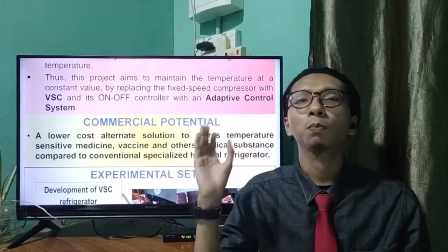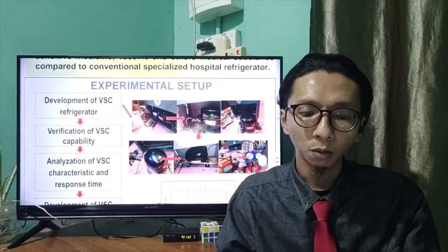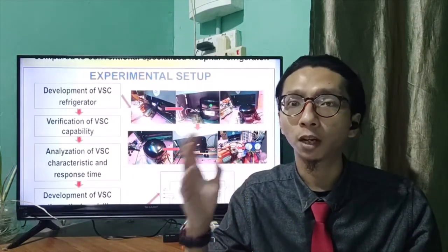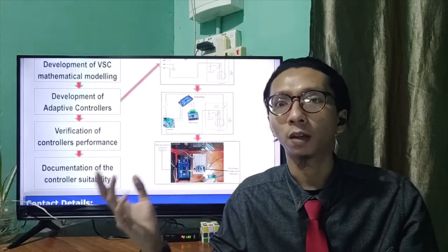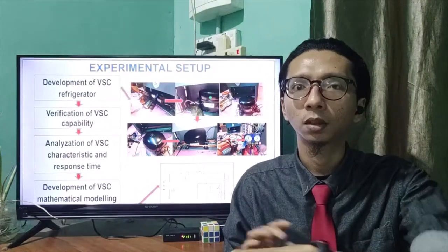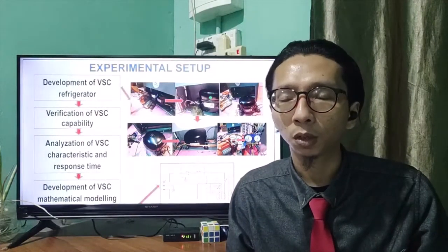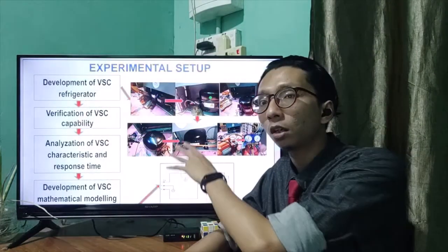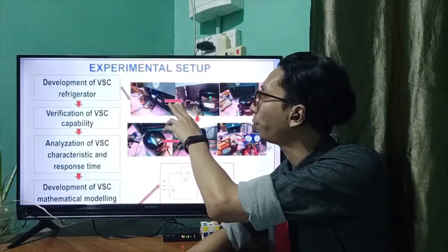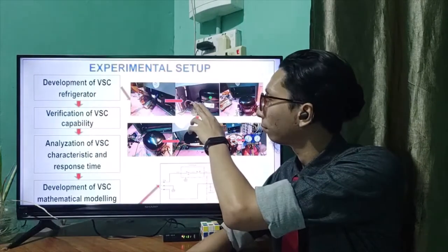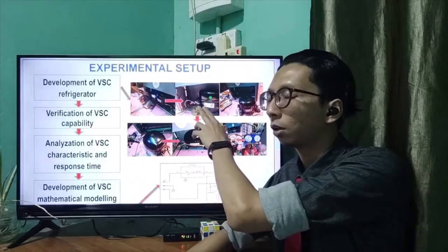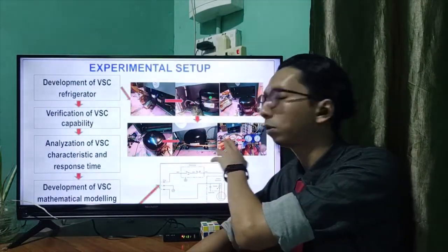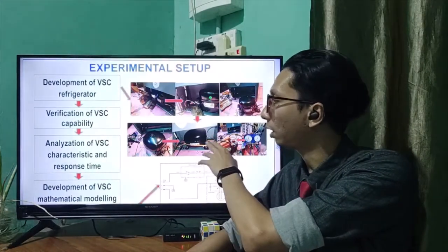Now I will talk about how my experiment is set up. My research is divided into two parts: first is the development of the variable speed compressor, and secondly is the development of the adaptive controller. For the development of the variable speed compressor, we need to remove the original fixed speed compressor from the system, which means removing the copper piping, removing the old refrigerant, and replacing it with the new variable speed compressor, then refilling it with refrigerant and making sure that it is working.